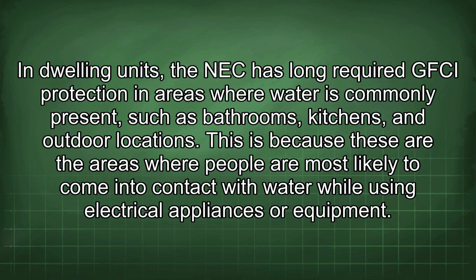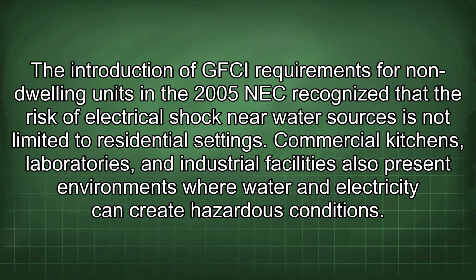In dwelling units, the NEC has long required GFCI protection in areas where water is commonly present, such as bathrooms, kitchens, and outdoor locations. This is because these are the areas where people are most likely to come into contact with water while using electrical appliances or equipment. The introduction of GFCI requirements for non-dwelling units in the 2005 NEC recognized that the risk of electrical shock near water sources is not limited to residential settings. Commercial kitchens, laboratories, and industrial facilities also present environments where water and electricity can create hazardous conditions.